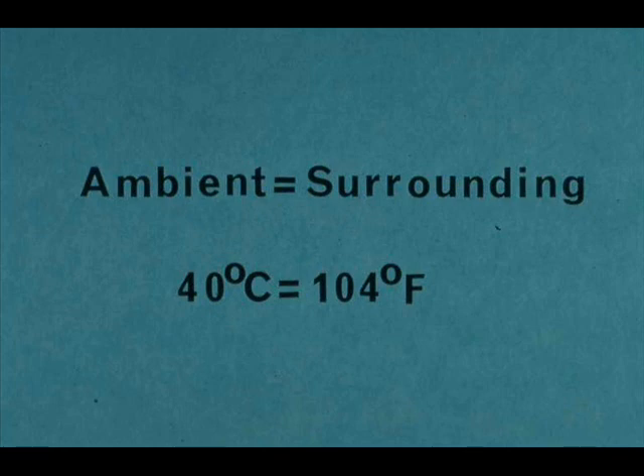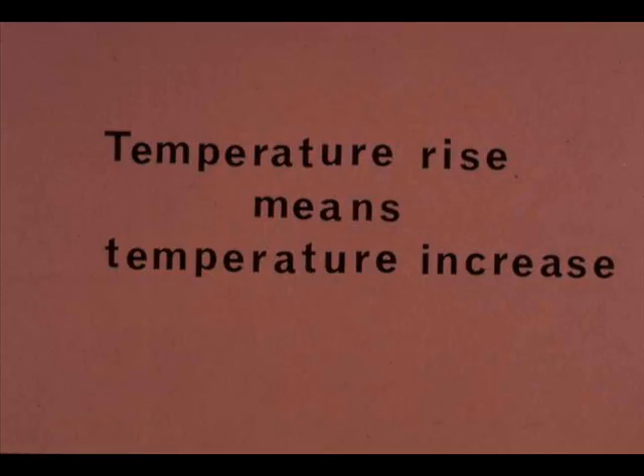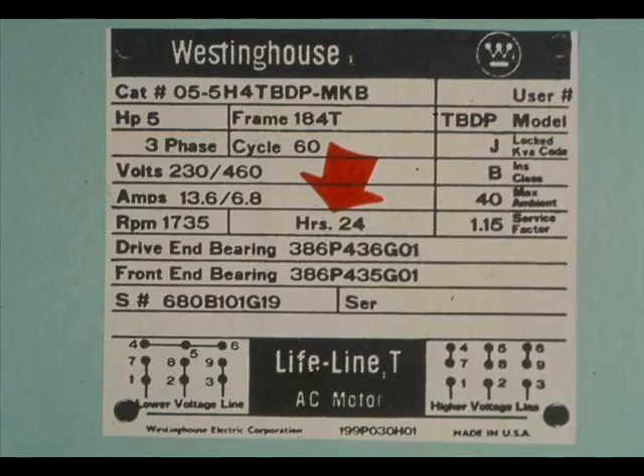Ambient means surrounding. This motor is designed for operation in a space where the temperature is not more than 40 degrees centigrade or 104 degrees Fahrenheit. Temperature rise means temperature increase, so the manufacturer could have chosen to rate this motor as rise 90 degrees centigrade. The time rating must be stated — that is, the length of time the motor can be run continuously without damage under design conditions. The usual ratings are 5 minutes, 15 minutes, 30 minutes, 60 minutes, and continuous. The time rating for this motor is 24 hours.